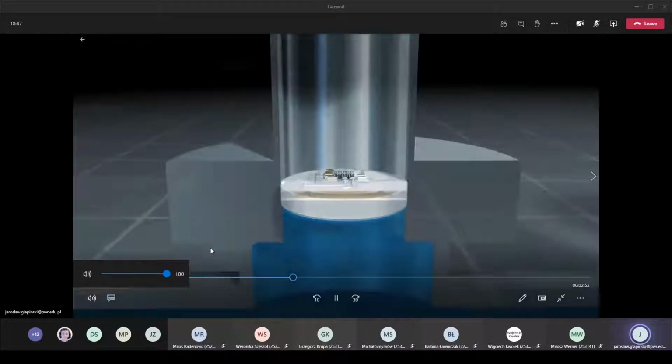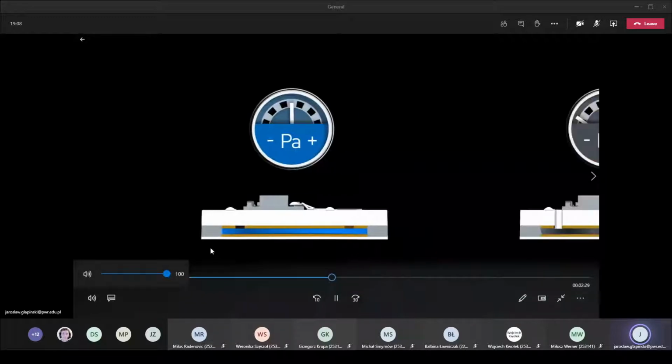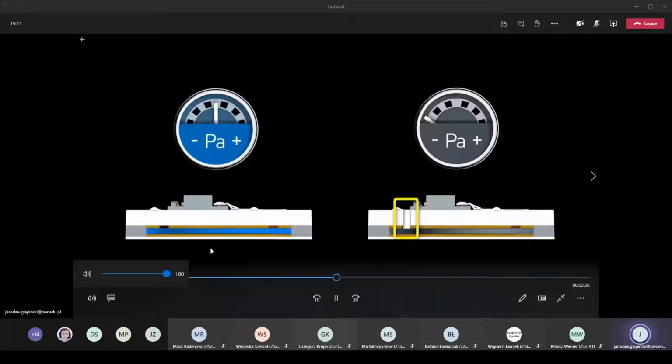In a ceramic cell, an electrically conductive material is applied to a ceramic substrate, thus forming a capacitor. As pressure is applied, the diaphragm deforms and causes a change in capacitance. The absolute pressure cell is a closed system and measures against the vacuum. In an atmospheric environment, the air pressure is indicated. In a gauge pressure cell, an opening in the substrate permits the pressure compensation between the atmospheric environment and the inside of the cell. The cell measures values which are relative to the ambient pressure. In an atmospheric environment, the air pressure is not indicated.